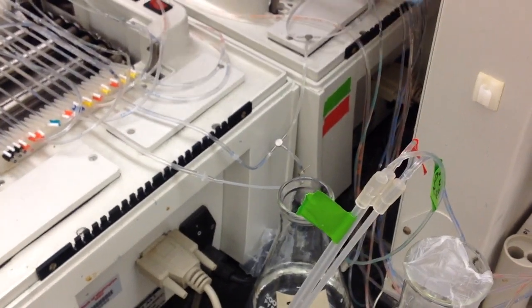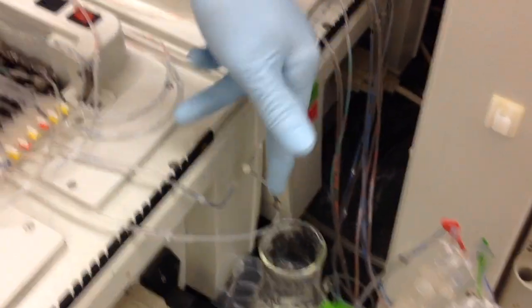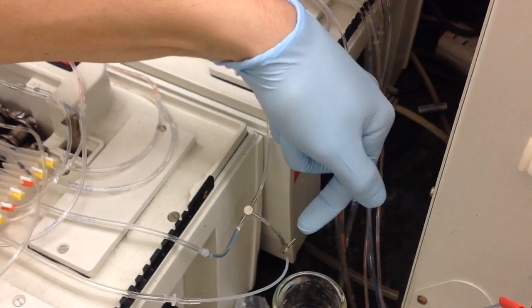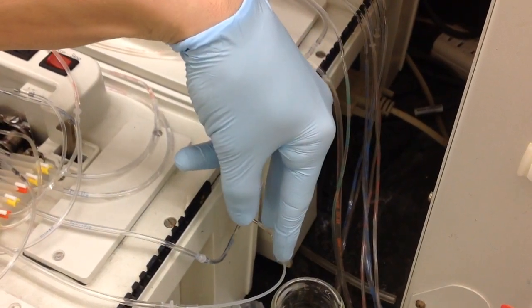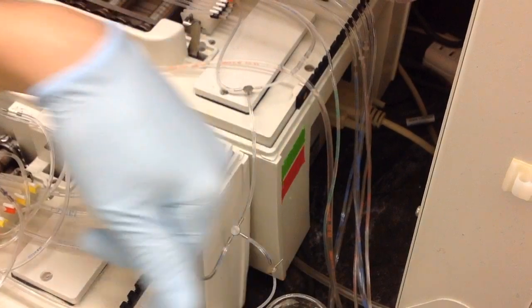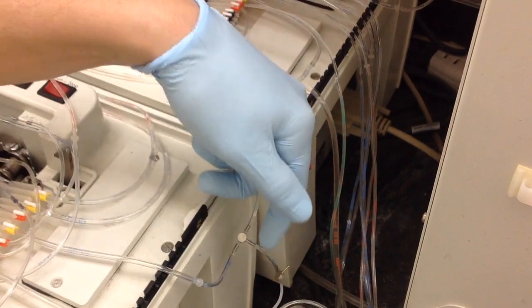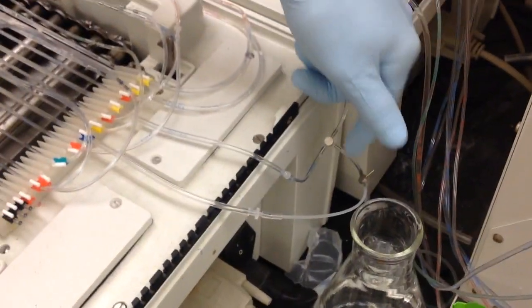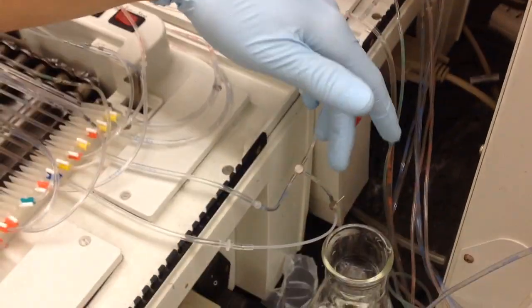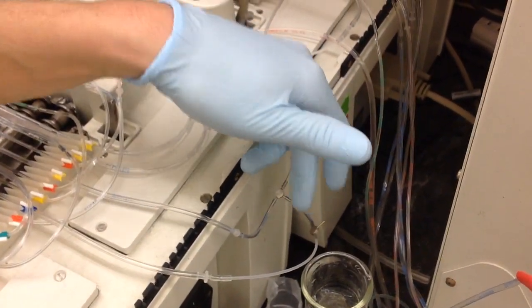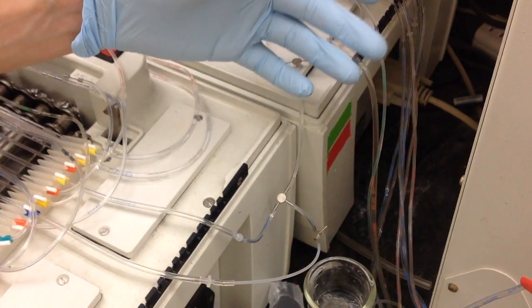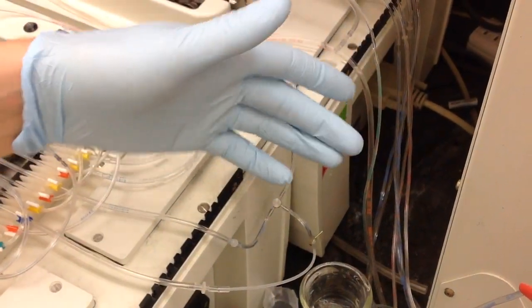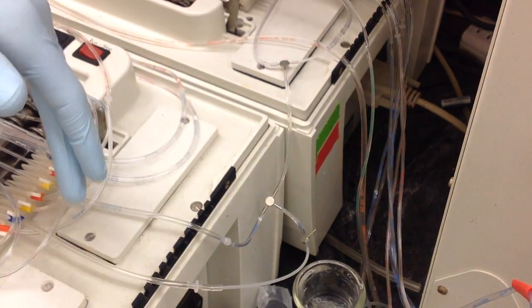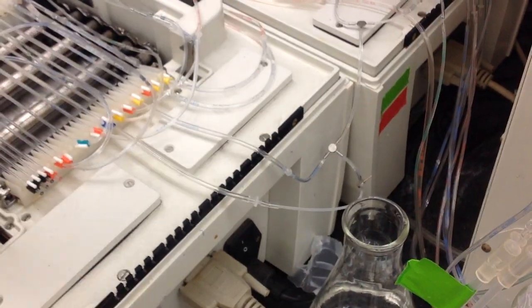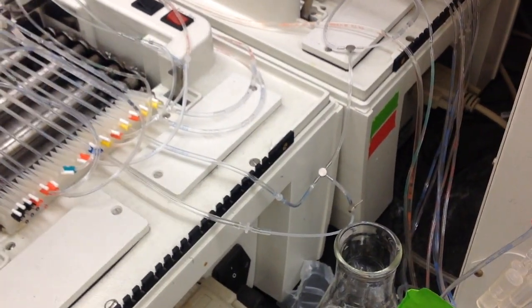Every time the probe comes up, you're going to get what they call the inter-sample air bubble, and you can watch it come through and split off. It comes through this main line that I just took off, and it splits here. Say all of the air is going into this channel, or this side, rather than splitting off there. There's probably a clog in there, or something's not airtight. So try to adjust it. But if you really can't adjust it, and all the air is going to one side of the T, then it's time to replace it. Other than that, you shouldn't have to worry about the metal pieces.